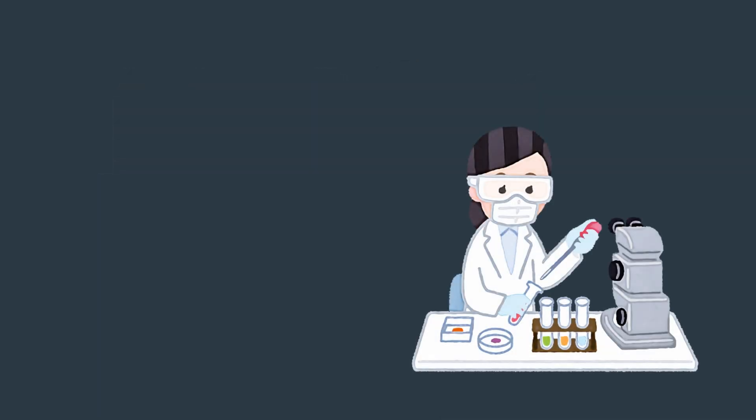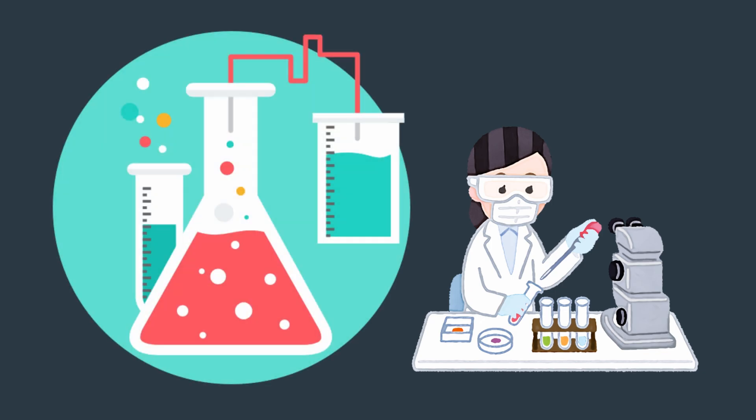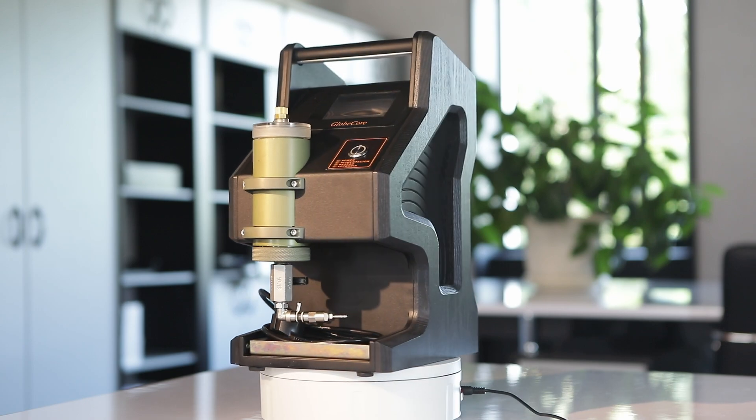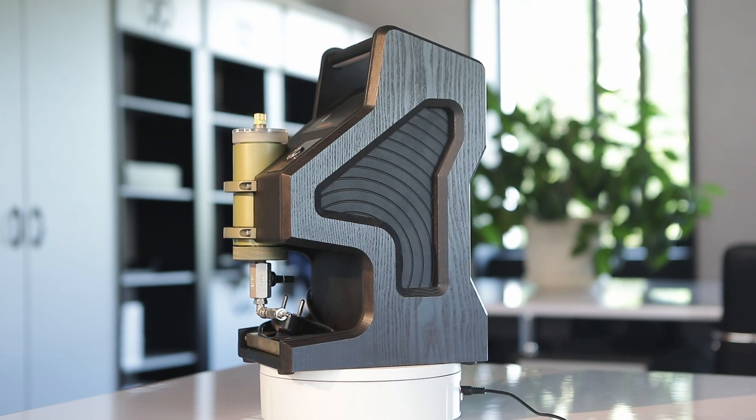used for this purpose. Chromatographic analysis is a long and labor-intensive procedure, but if you need to get a result quickly, you can analyze the key gas only, namely hydrogen, with the use of TOR-2. You can take a transformer oil moisture and hydrogen test.